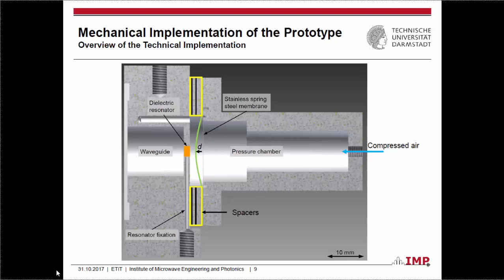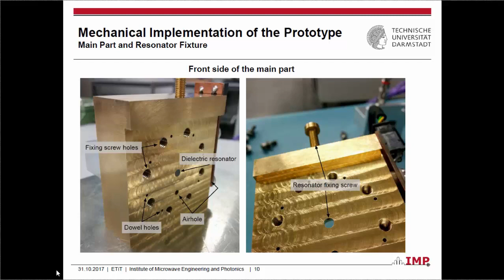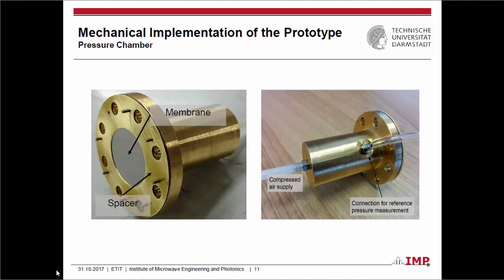Here we can see two pictures of the main part of the transducer. Here the waveguide with the dielectric resonators, another perspective view with the fixing screw to fixate the resonator in the waveguide. Here the pressure chamber with our membrane and a mounted spacer, and here the compressed air supply and also the connection for the reference measurement system.